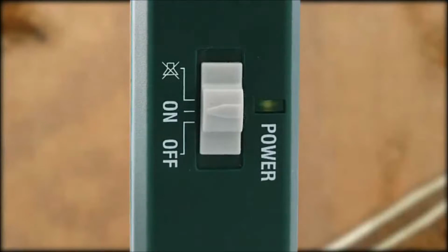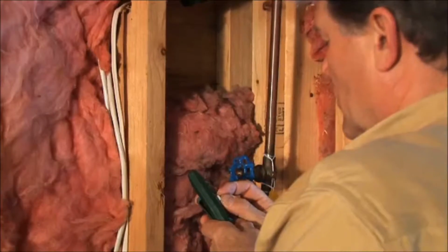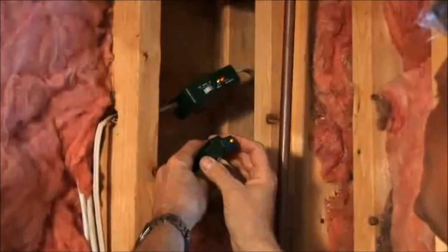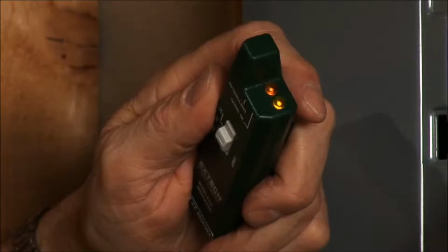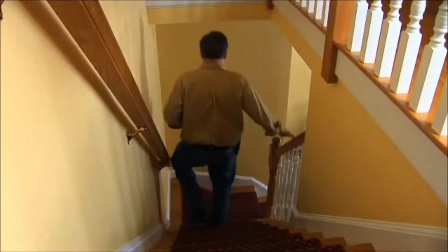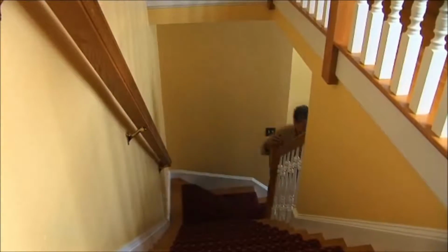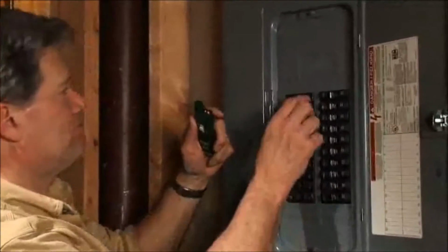Switch the receiver unit to on. If the cable under test has voltage, you will hear a tone, and the amber LED on the top of the unit will turn on. Go down to the circuit breaker panel. Be sure that the yellow signal OK LED is on and stays on when you reach the breaker box.